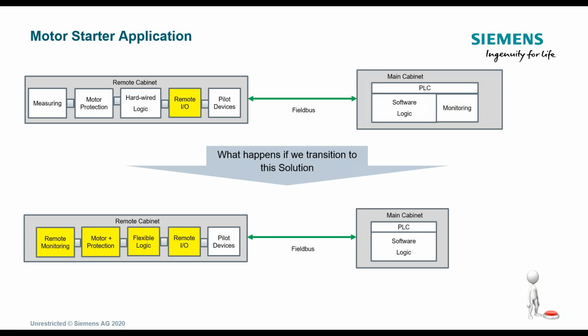Now go from field bus. Now that we move the monitoring out there, if you notice, we've put the remote I/O, logic, motor protection, and remote. We've moved all that out of the PLC, and we've moved it into the cabinet where the motor is, or it could be the bucket.